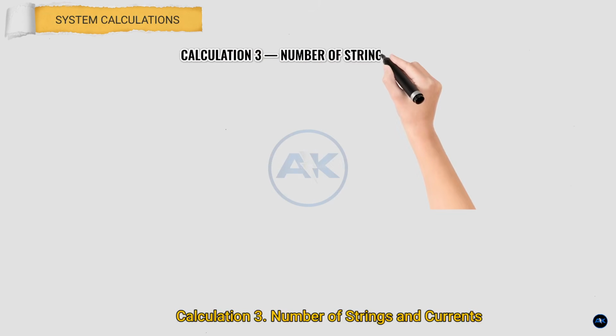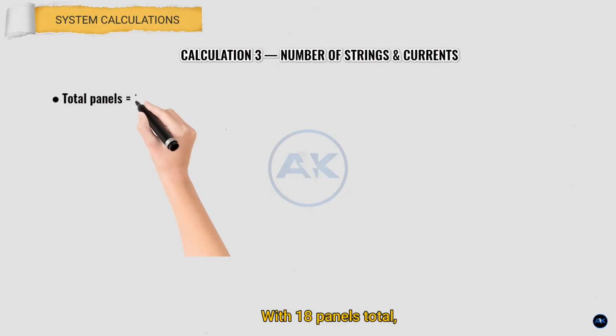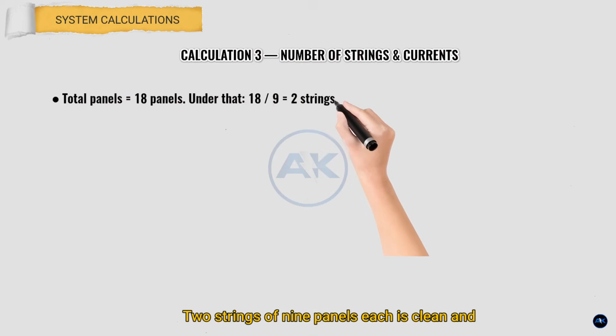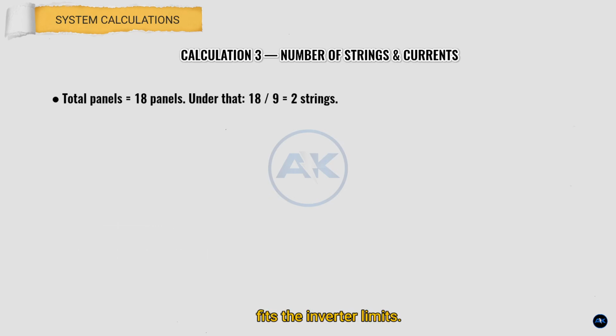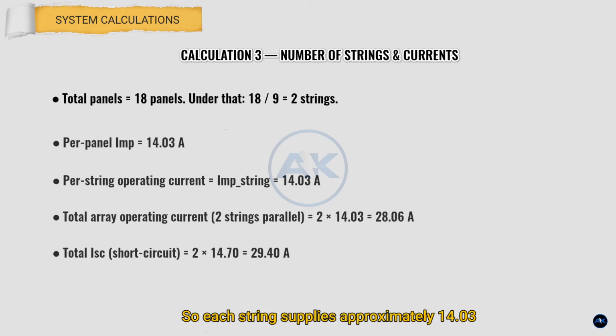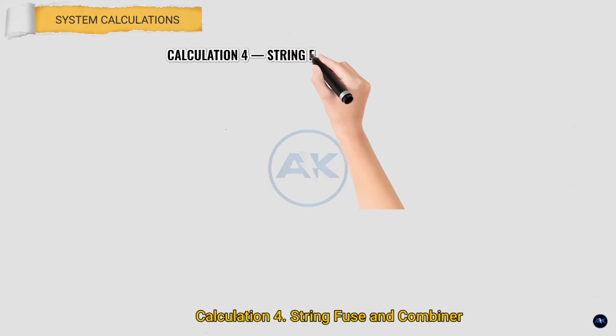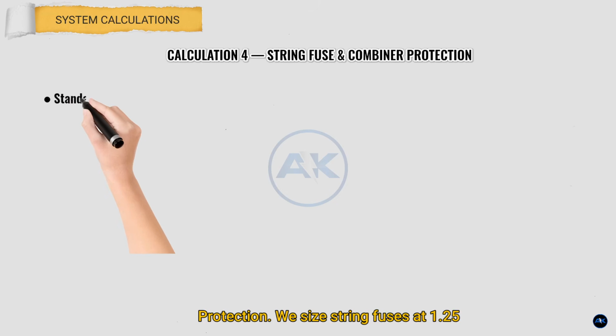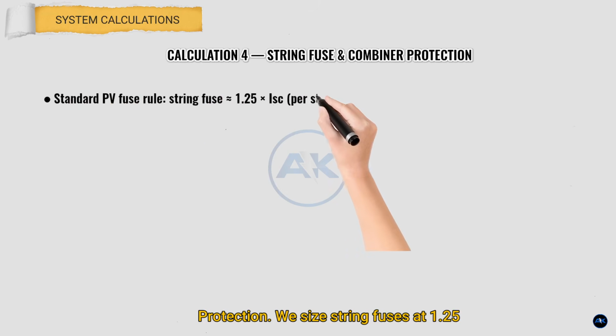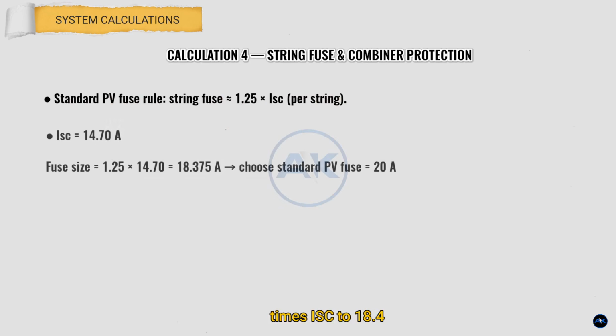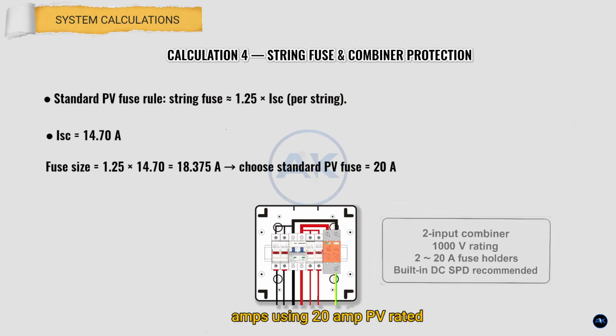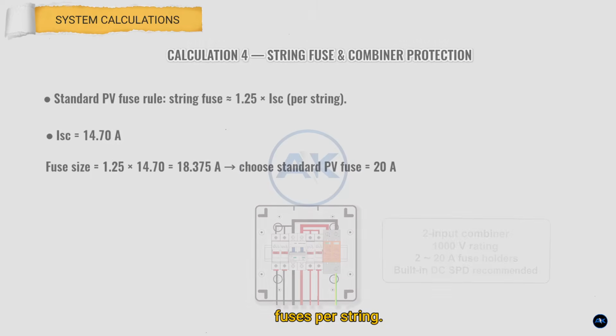Calculation 3. Number of strings and currents. With 18 panels total, 2 strings of 9 panels each is clean and fits the inverter limits. So each string supplies approximately 14.03 amps. 2 parallel strings give approximately 28.06 amps operating current and approximately 29.4 amps short circuit current. Calculation 4. String fuse and combiner protection. We size string fuses at 1.25 times ISC to 18.4 amps, using 20 amp PV rated fuses per string.